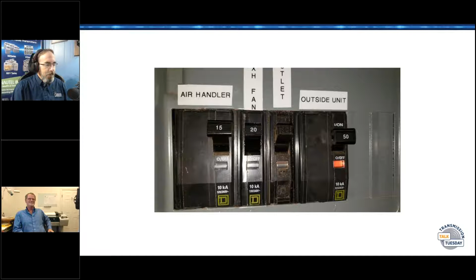And you walk over and you see water in the condensate bowl. First you think, uh-oh, we're getting moisture in the line. Well, there's almost no perfect rigid transmission line, especially the longer they get. At some point you're going to have some moisture build up, it's almost unavoidable, especially after a few years. But what was actually going on with this one wasn't a problem so much with the line.